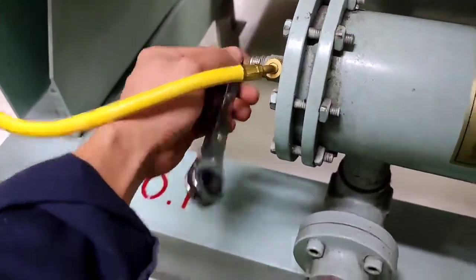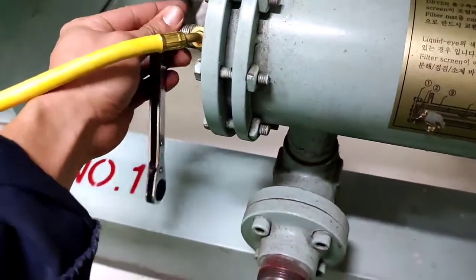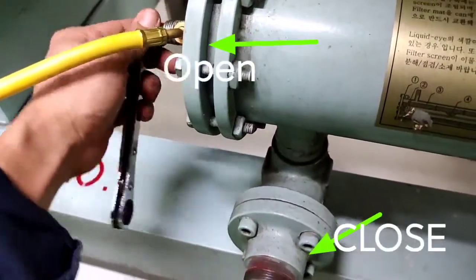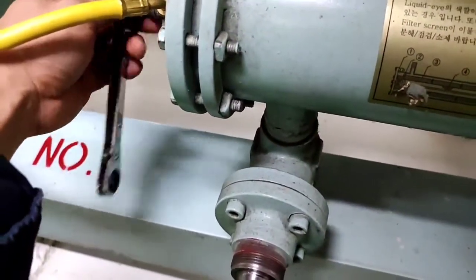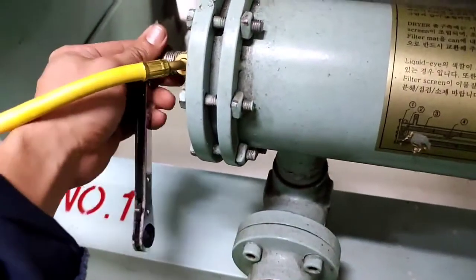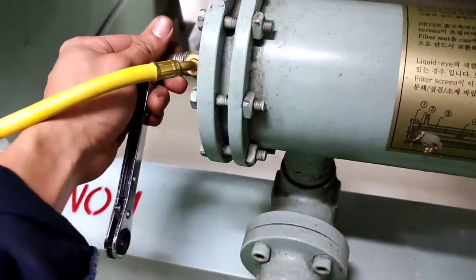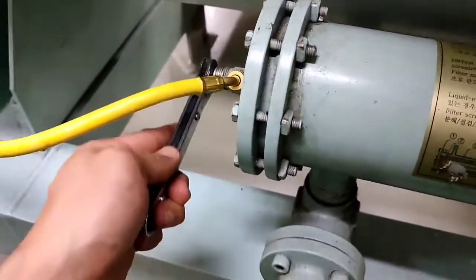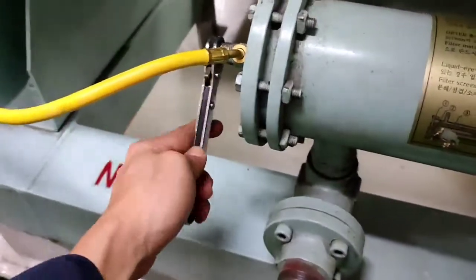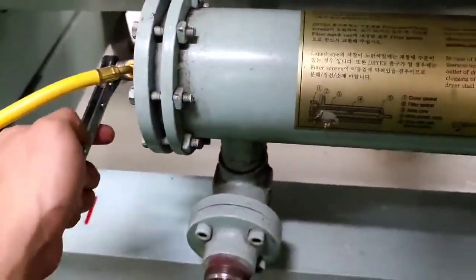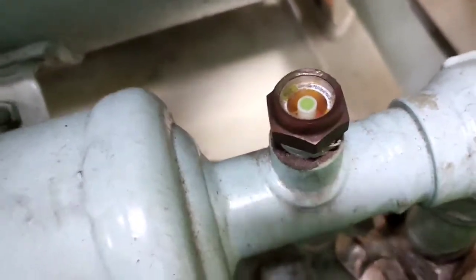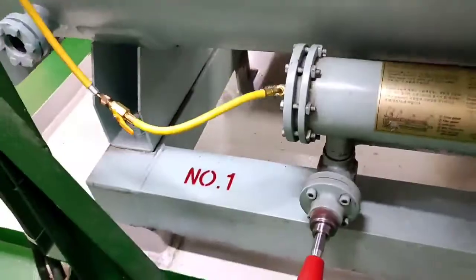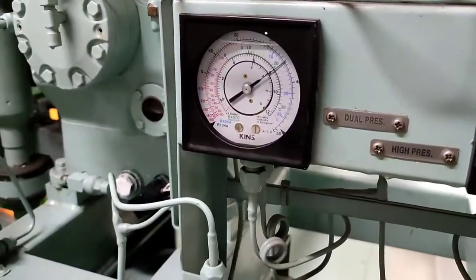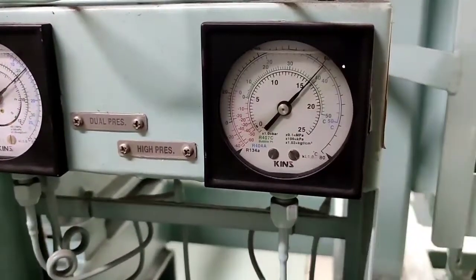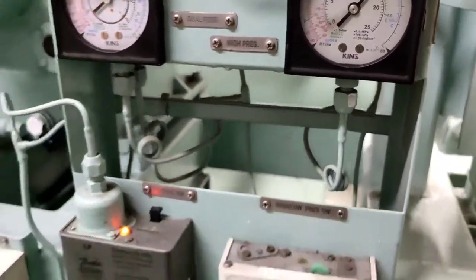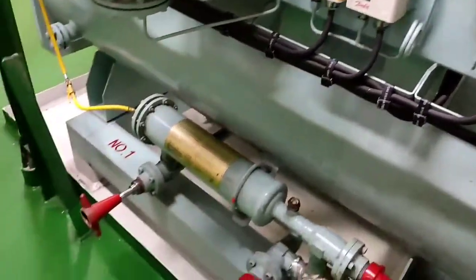Okay, just open all charging valves, system 1 and system 2. After opening those, you need to bleed, so that there is no air inside the hose. Right now, system 2 has charged refrigerant, and then we put it back to number 1. It means number 2 refrigerant going to number 1.